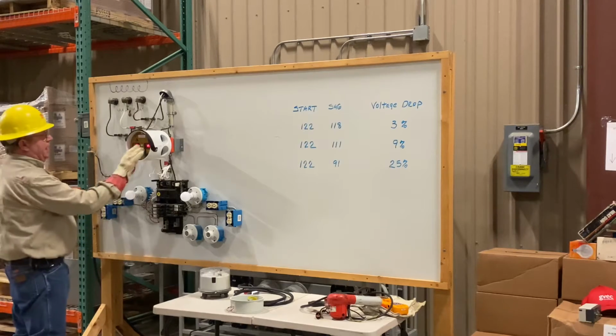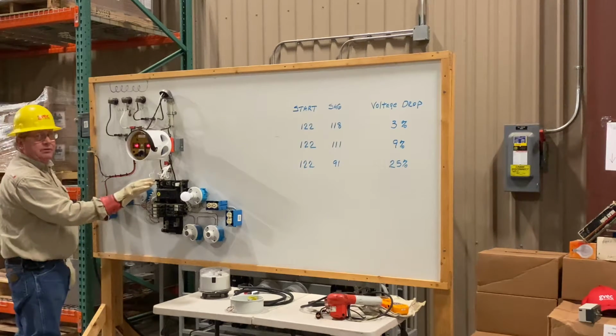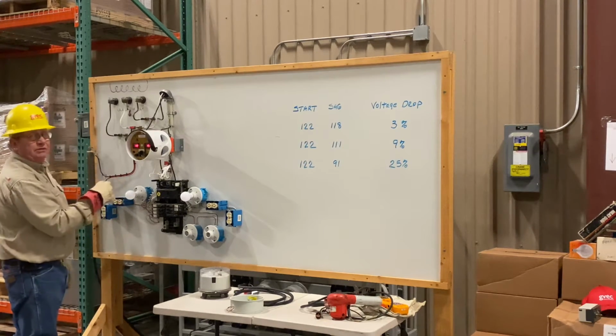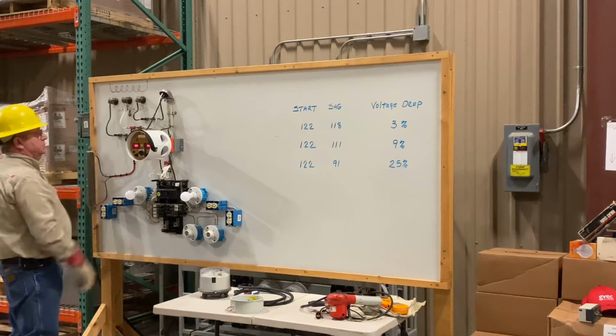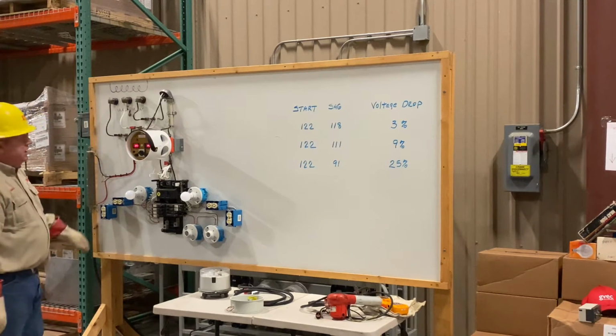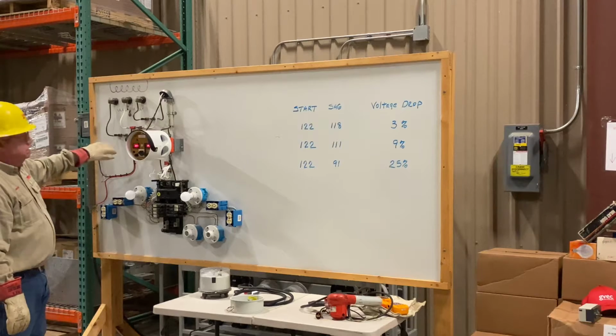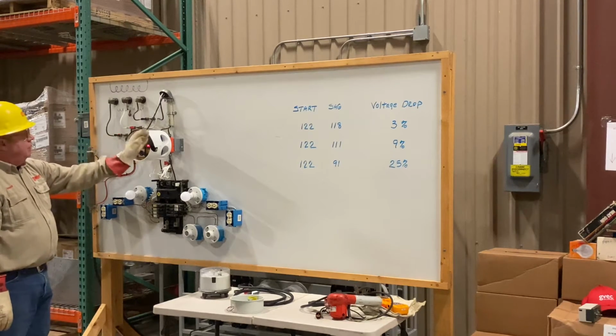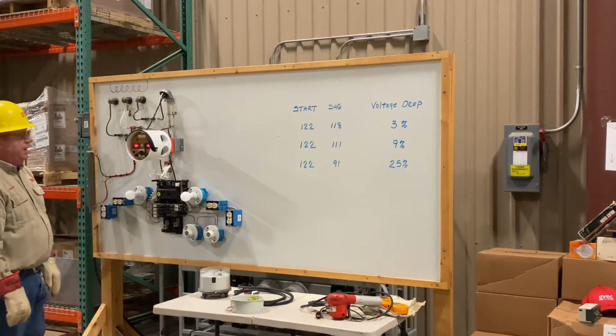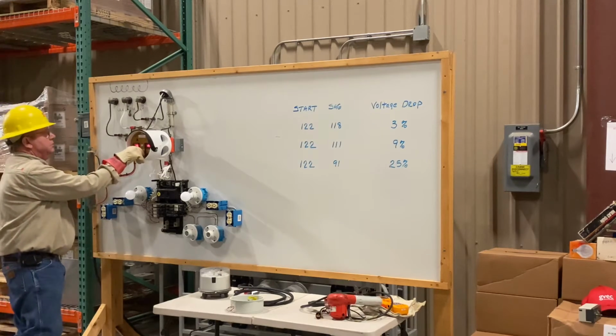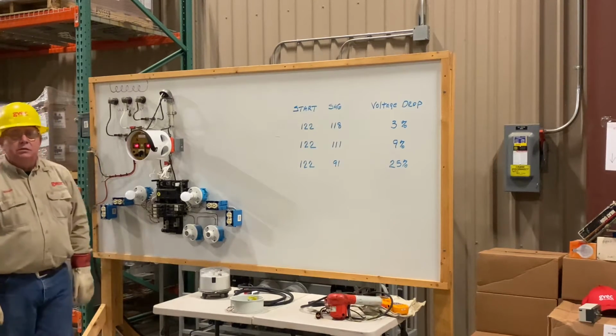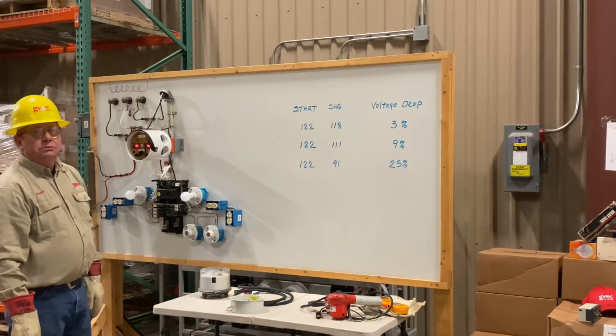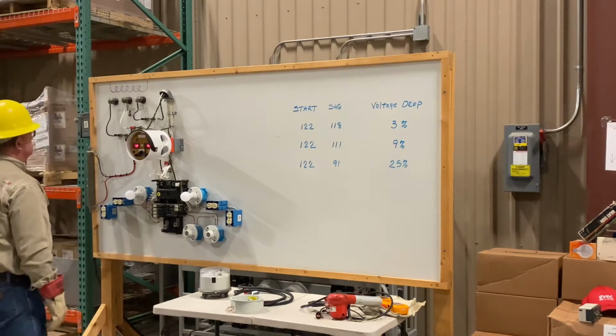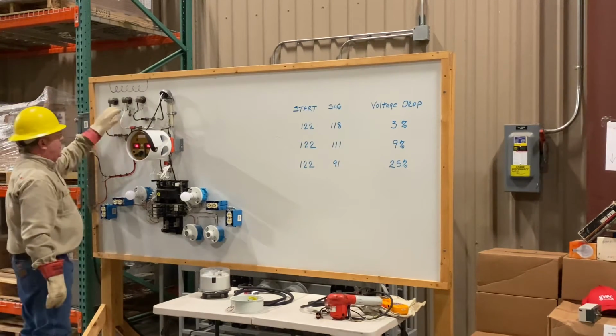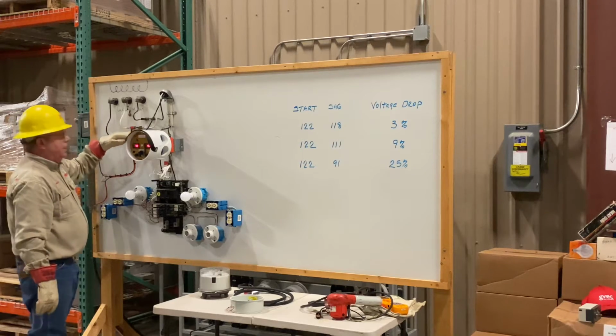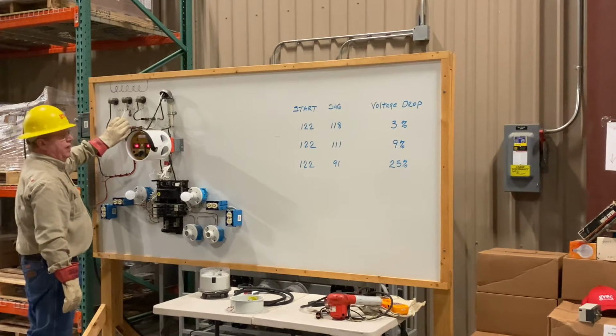Now we're going to take that load that we had put on the right-hand side, and we're going to put it on the left-hand side. Now we watch the 91 move over here. The 147, 148 is now on the right-hand side. That's a guaranteed neutral connector. Guaranteed. Now, I have created the bad neutral connector in the service run. I'm going to restore that.